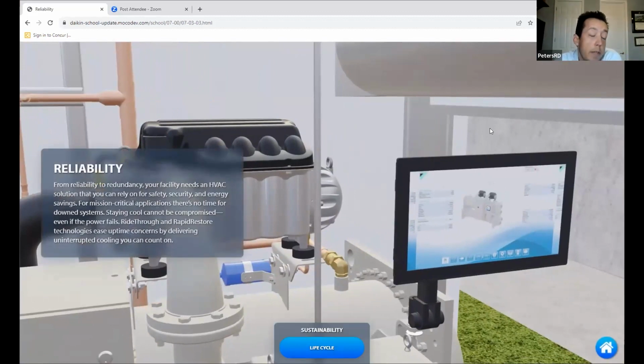In terms of reliability, there's a lot of technology in the Daikin WME or WMC chiller. One great feature for mission critical or even standard operation is the ability to ride through or have rapid restore. I saw it recently at our factory in Virginia—you can shut the power off completely, and that chiller's compressor is able to ride through and come back online. So if you have dirty power, surges, or lightning storms, this type of chiller adds reliability for the client.